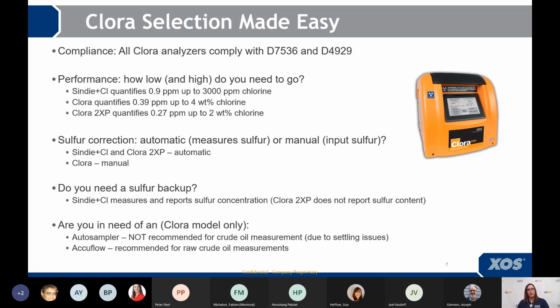Okay. So in our good category would be the Sindie plus chlorine analyzer, which quantifies 0.9 ppm up to 3000 ppm chlorine. And then our Clora analyzer in the better category, which is about 0.4 ppm up to 4 weight percent chlorine. And then our Clora 2XP, which is our best offering, quantifies 0.27 ppm up to 2 weight percent chlorine. Now, some of you might be scratching your head here saying, these numbers are a little higher than what I've seen on the brochures. And you'll want to keep in mind that the limits of detection on the brochures are the limits at which we can see the concentration of the element that you're looking for.